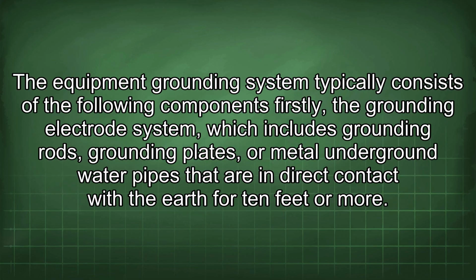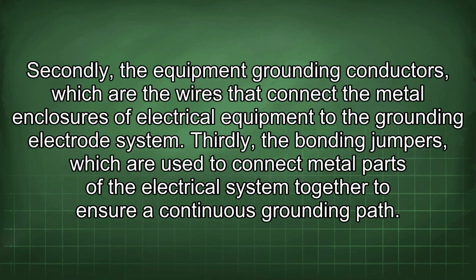The equipment grounding system typically consists of the following components. Firstly, the grounding electrode system, which includes grounding rods, grounding plates, or metal underground water pipes that are in direct contact with the earth for 10 feet or more. Secondly, the equipment grounding conductors, which are the wires that connect the metal enclosures of electrical equipment to the grounding electrode system.